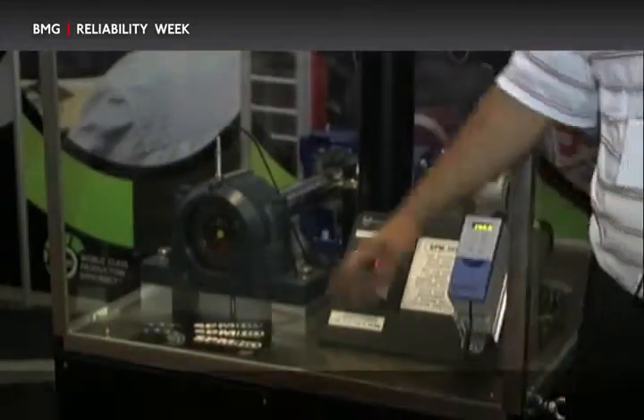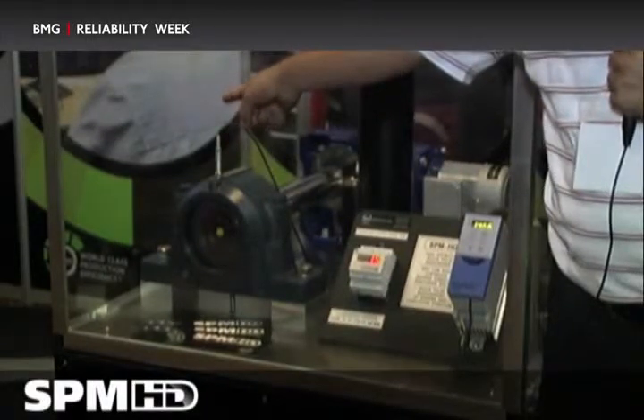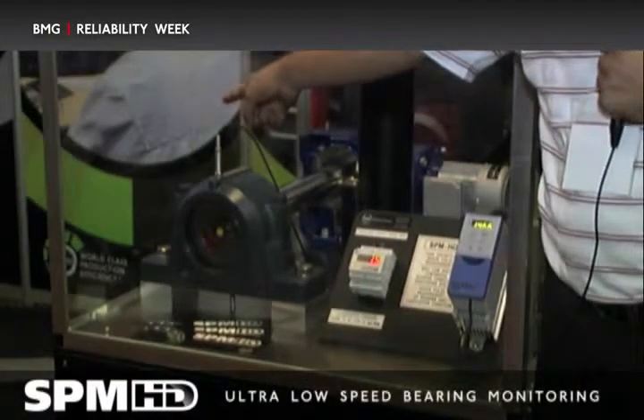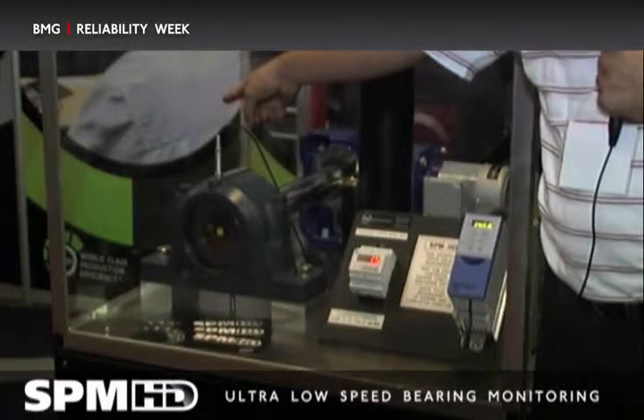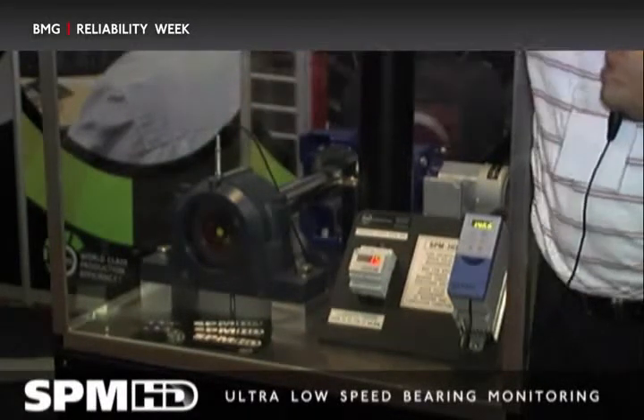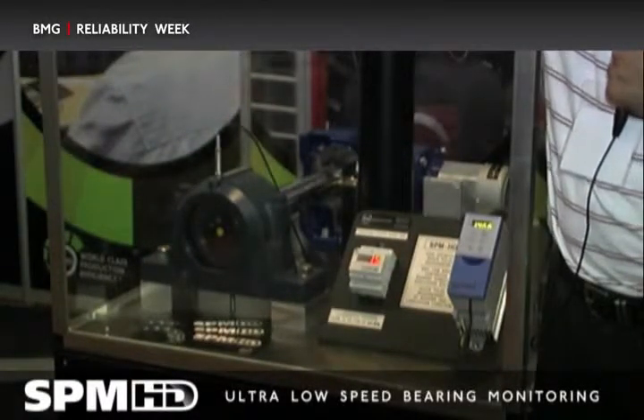The big difference between vibration and the shock pulse method is that previously vibration was only able to measure down to around 30 RPM. But with the shock pulse method, we are now able to measure and monitor applications down to 1 RPM. The shock pulse transducer is permanently installed onto the bearing housing, and the signals measured can be displayed on a screen like we have there.